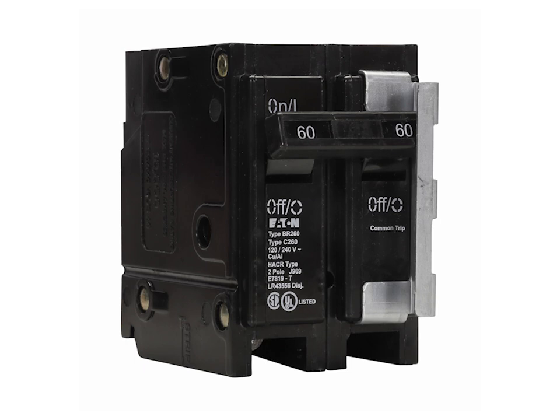This requirement primarily applies to your hardwired dishwasher circuit. The next states, the branch circuit overcurrent device shall be permitted to serve as the disconnecting means where the switch or circuit breaker is within sight from the appliance or is lockable in accordance with 110.25. Within sight from the appliance does not only mean that while flipping the switch the electrician can see the appliance, it also means that while servicing the appliance, the switch can be seen by the electrician and it is within 50 feet. If it doesn't meet the within sight requirement, the circuit breaker is required to be lockable.